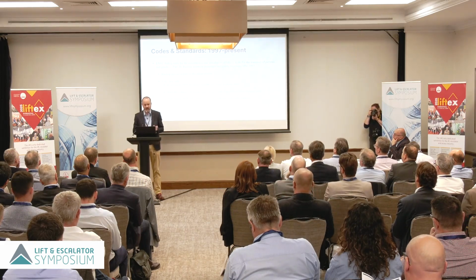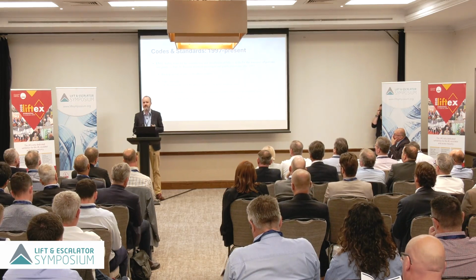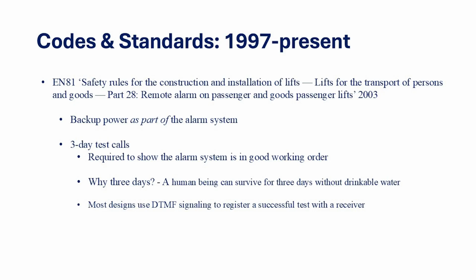So the alarm has to dial out every 3 days, essentially as a proof of life. I can dial out, I'm working. It has to be dialing out because dialing in doesn't prove your call chain. I constantly get asked this, why every 3 days?